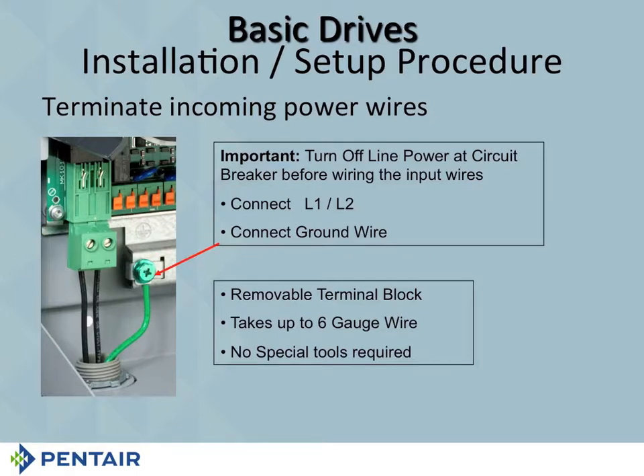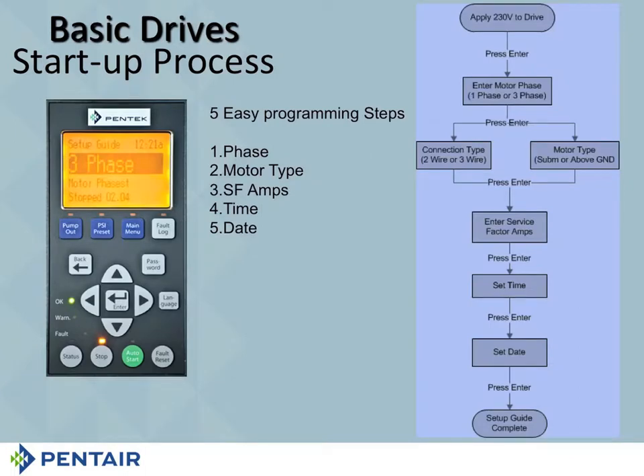Your ground will go all the way through the box, then back to your disconnect switch, and then from your disconnect switch back to the main breaker box. And yes, you really, really should have, for safety's sake, a disconnect switch between the VFD and the main breaker box. There really should be a disconnect switch there. So take it all the way back to the main breaker box, and your grounding shouldn't have any problems at all. Now, startup. Startup looks like this.